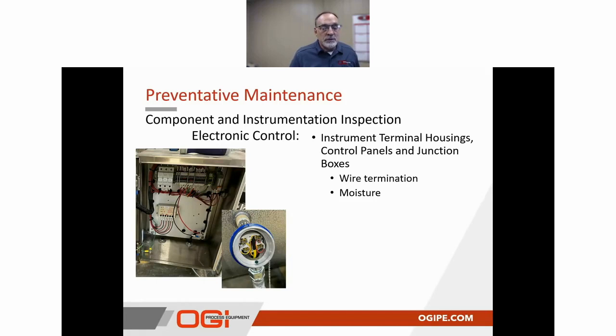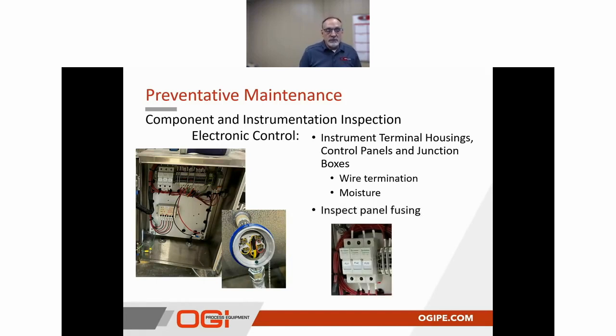We also want to inspect the panel fuses for control panels of any type to ensure that we have the right size fuse, or that a fuse hasn't been changed out just to keep something running for some reason. We want to make sure the right fuse is installed, as well as that the fuses are good, so we're going to check continuity on those fuses to make sure that they're in good shape.